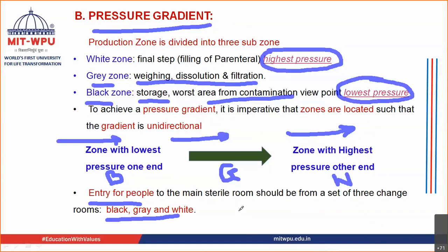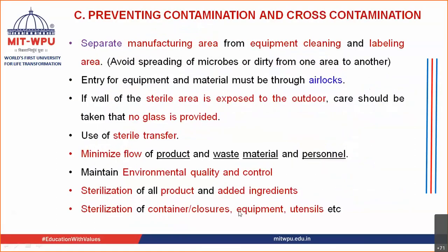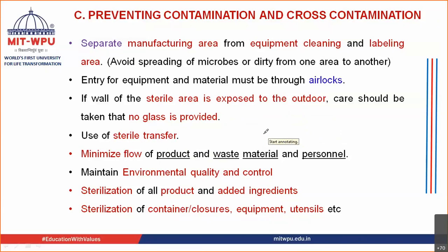Maintaining the pressure gradient is an important facility requirement in the parenteral manufacturing section. To prevent contamination and cross-contamination, each area — manufacturing, equipment cleaning, and labeling — must be separated. Cross-contamination means the spreading of microorganisms, dirt, or pyrogens from one area, substance, person, or equipment to another.